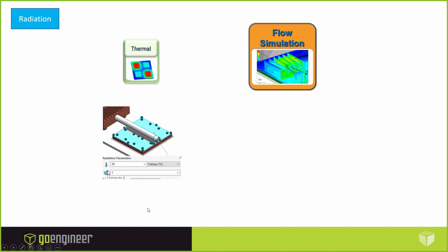And the emissivity just describes how well it radiates. If you key in a low emissivity, it has little radiation, and an emissivity of 1 is its maximum value for radiation. Things like asphalt or black tar would have a very high emissivity because they're going to emit as well as absorb all the incoming radiation.